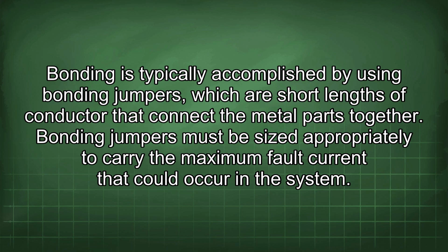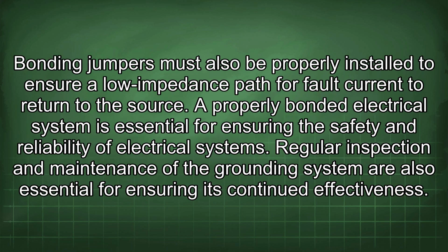Bonding is typically accomplished by using bonding jumpers, which are short lengths of conductor that connect the metal parts together. Bonding jumpers must be sized appropriately to carry the maximum fault current that could occur in the system. Bonding jumpers must also be properly installed to ensure a low impedance path for fault current to return to the source. A properly bonded electrical system is essential for ensuring the safety and reliability of electrical systems.